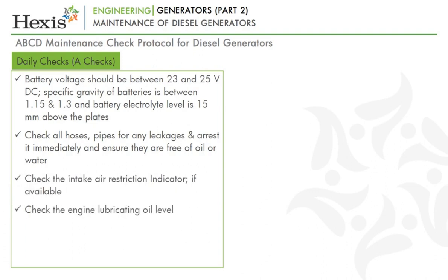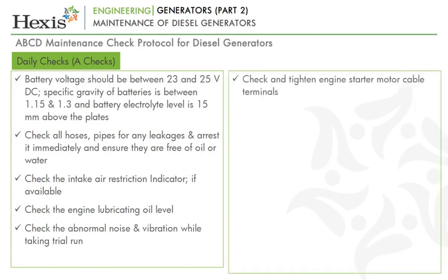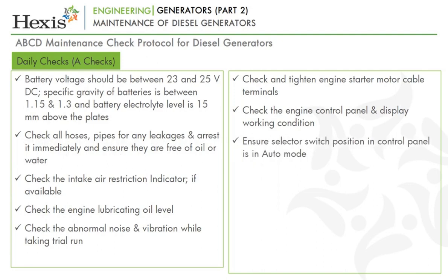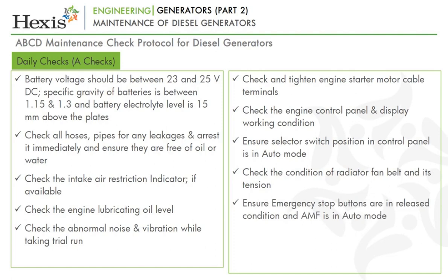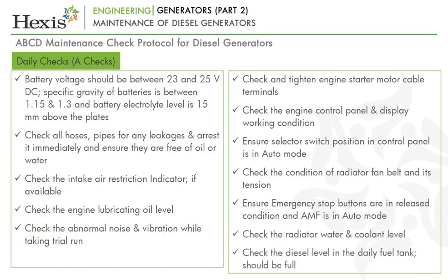Check the engine lubricating oil level. Check for abnormal noise and vibration while taking a trial run. Check and tighten engine starter motor cable terminals. Check the engine control panel and display working condition. Ensure the selector switch position in control panel is in auto mode. Check the condition of radiator fan belt and its tension. Ensure emergency stop buttons are in released condition and AMF is in auto mode. Check the radiator water and coolant level. Check the diesel level in the daily fuel tank; it should be full.